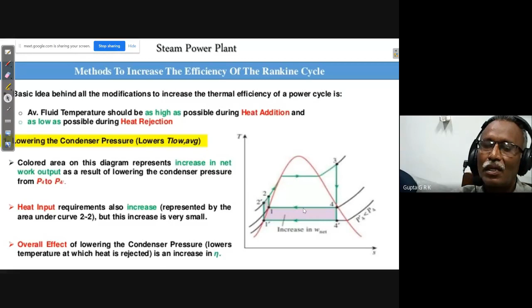Some more things. P condenser cannot be lower than the saturation pressure corresponding to the temperature of the cooling medium. That's what I told. The temperature of the cooling medium is some 35 degrees outside, and I cannot decrease this below that. So there cannot be heat transfer, there cannot be condensation. And lower P condenser creates the possibility of air leakage into the condenser. If I want to maintain the condenser lower than the atmospheric pressure, air leaks into it. So I should have a de-aerator like thing. I have to remove the air that is trapped.